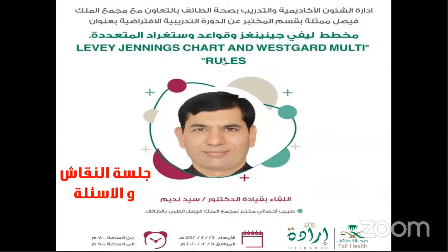This is a good question. A calibrator is a fixed value which is used to calibrate the machine to give you a graph on the basis of which you will assess your daily samples and controls. So the calibrator has a fixed value. You have a known quantity of the analyte. The analyte means the substance which is being tested.